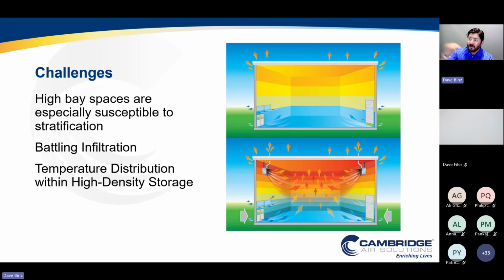Because I may have low ventilation requirements, most warehouses, distribution, and existing facilities have really inadequate ventilation to overcome infiltration. When it gets really cold in the ambient winters, I've got high winds coming across, I've got stack effect and stratification. Sometimes this infiltration becomes a very sore thorn in our side to making comfortable conditions. And many times when we look at industrial retrofitting of warehouses, we've got lots of dock doors, perimeters that are very cold and drafty because of inadequate ventilation solutions. We'll talk a little more about that.